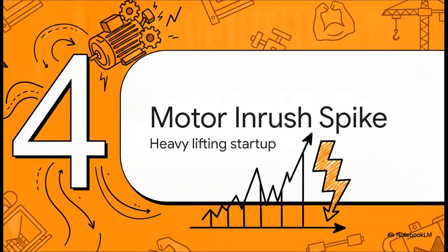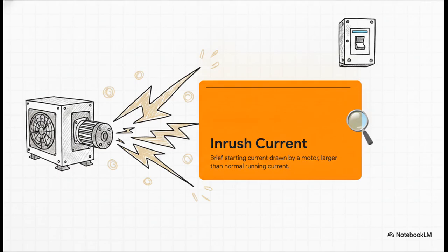Section 4, the motor inrush spike, the heavy lifting of starting up. So, inrush current is a brief starting current drawn by a motor that is significantly larger than its normal running current. When your AC compressor kicks on, it takes this massive, greedy gulp of electricity just to get those heavy mechanical parts moving. It's exactly like pushing a stalled car. It takes a massive, exhausting effort to get it rolling, right? But it's way easier to keep it moving once it starts.